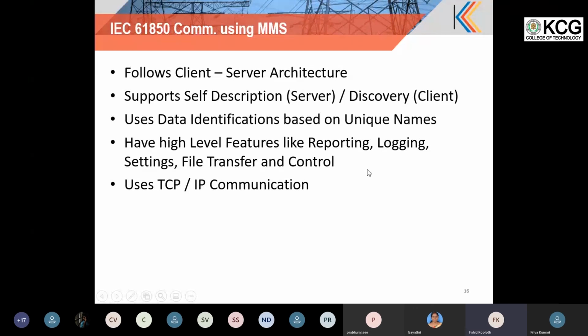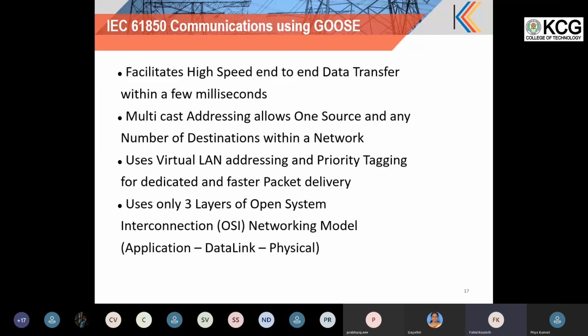Then moving on to GOOSE. MMS, as I have mentioned, completely relies on TCP/IP. So all the reliability mechanisms adopted in TCP/IP are applicable in MMS, and retransmission and a lot of other parameters are there to enable reliability on a TCP/IP network. But GOOSE needs to be sent out on a faster basis. So it does not have the flexibility to send the data over the TCP/IP layer. It needs to go directly to the OSI networking model, Ethernet.